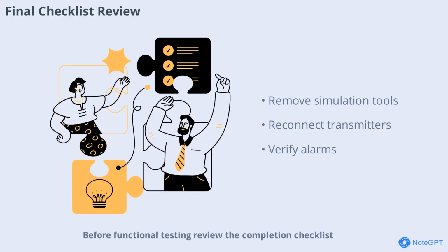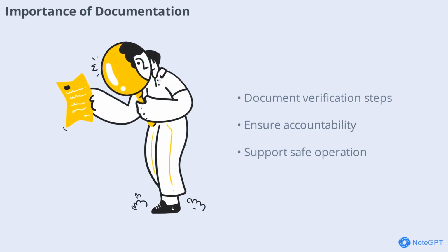Before functional testing, review the completion checklist, remove simulation equipment, reconnect transmitters, verify alarms, and ensure no active forces remain in the PLC. This final step guarantees system readiness and safety. Documenting every step of I/O verification is crucial for accountability and traceability. Proper records ensure that all tests are completed, issues are resolved, and the system is ready for functional testing. This practice supports safe and reliable operation.